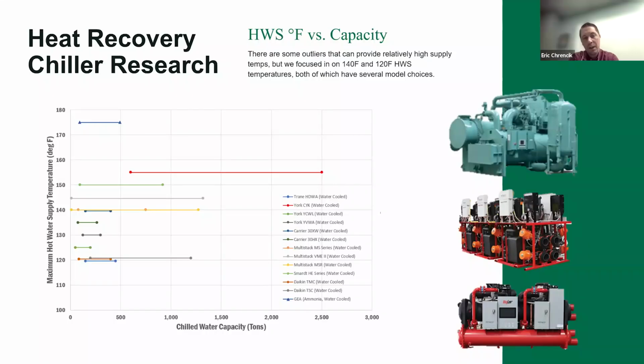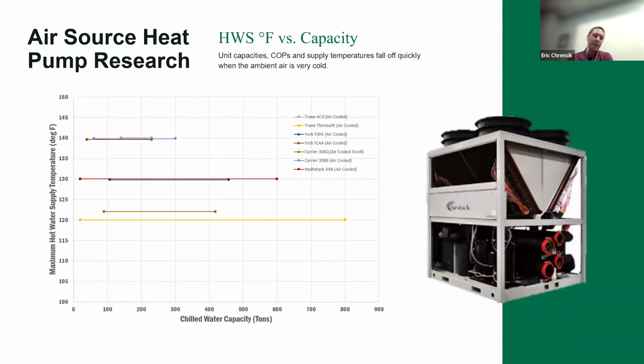Yeah, hit the next slide. And same thing here, this continues to evolve. You can get 2-pipe type and 4-pipe type, right? So 2 pipes coming out or 4 pipes coming out, and you can get like 5 modes of operation. Heavier heating or heavier cooling while simultaneously doing the load, all heating or all cooling using the air as your source, or just full simultaneous 100% loaded up. With these, we've looked at big farms or fields of air source heat pumps, and depending on your system and how you're trying to configure it, it could potentially be used in lieu of a ground source heat exchanger, depending on what you're doing.